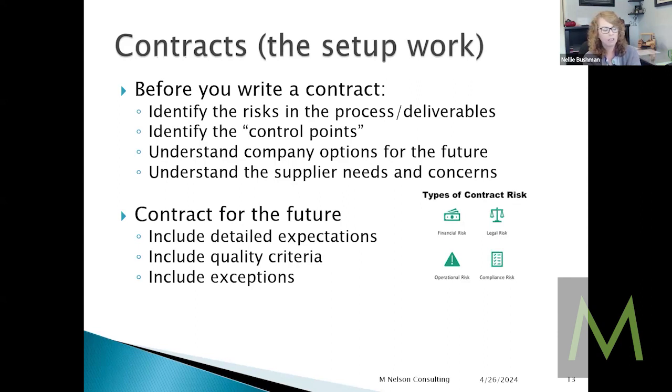I actually had an instance where I was in an FDA audit, and they sent the LHRs, and they were all in Chinese, and so then the auditor wrote us a 483 saying, you don't have them translate your lot history records. Because the client negotiated on demand, it was out of my control. I never saw them because I didn't need them. And so I'm like, well, I guess we're going to have to accept this one. So, there's all kinds of issues.